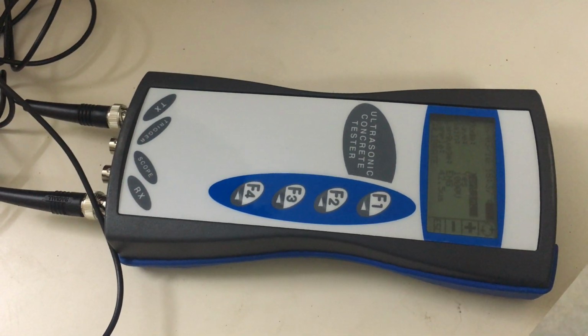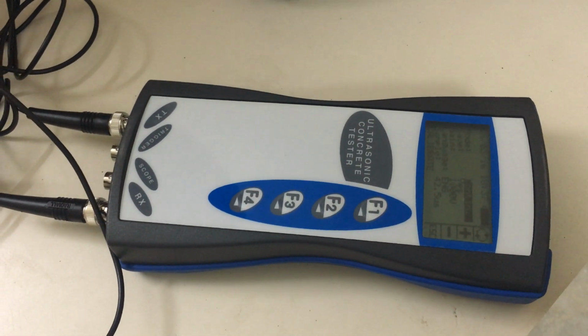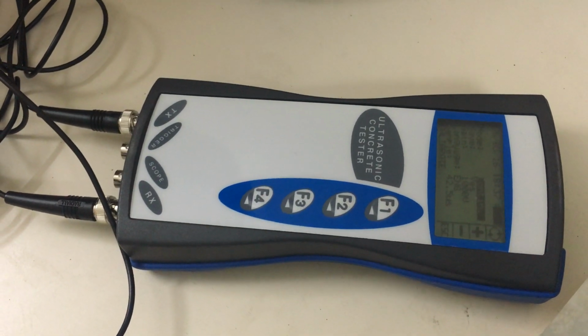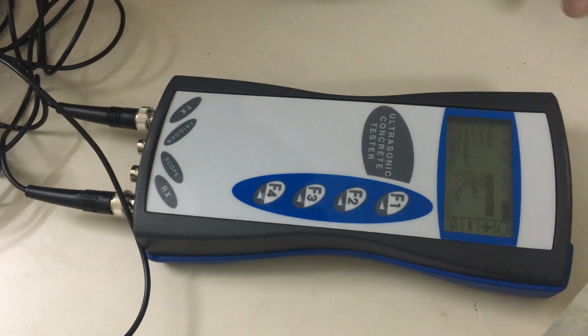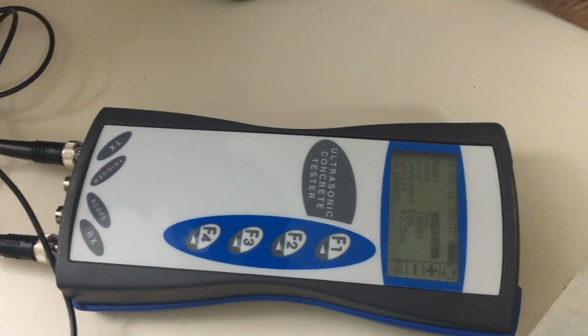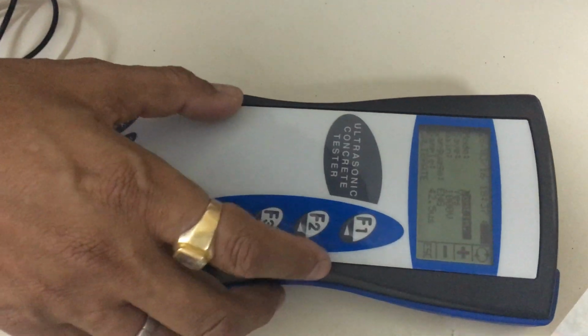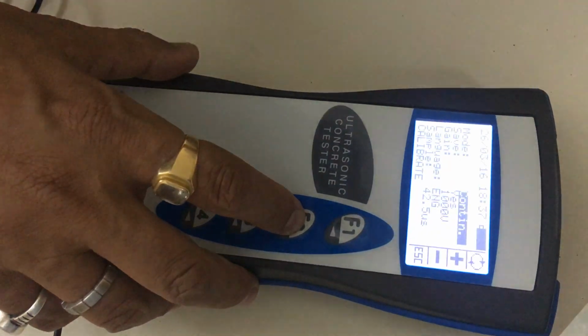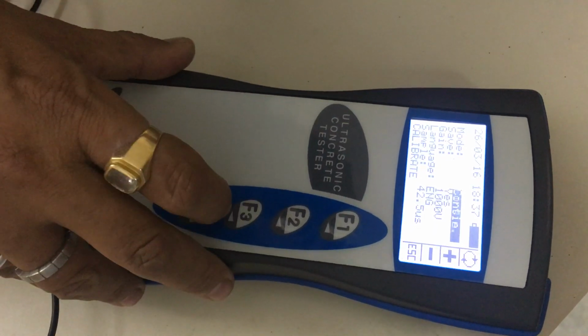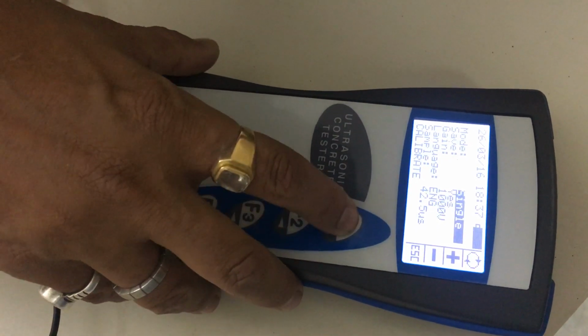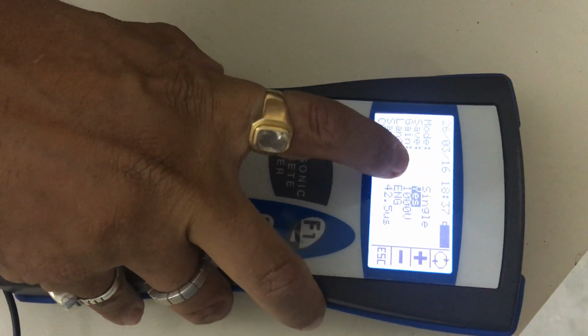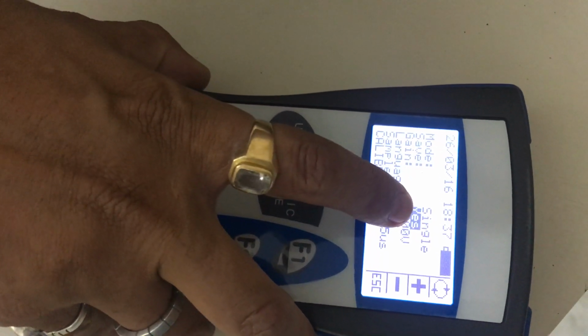In continuous mode, it does the same, but it does it 3 times and then records it, and keeps on continuously measuring the value as long as you do not press the stop key. So you can select continuous mode or single mode by the up or down arrow key. Continuous, single. Now go to the scroll key, go to another panel, save. If you keep this function yes, that means it's the automatic saving of your data. It keeps on saving the data.